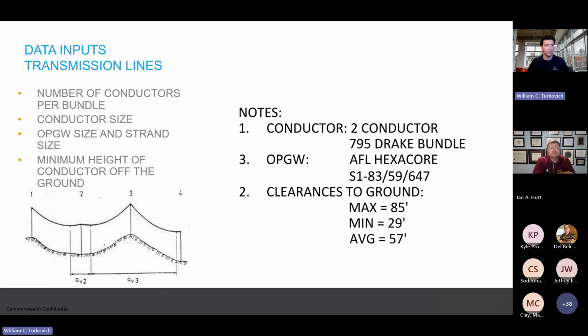The picture on the bottom left shows a transmission line going across bumpy terrain, we'll say. The line sags, and you can see there's a minimum point that's closer or farther from the ground where the lines are. We need to find that point because, as we said, both of these fields are distance driven, meaning the closer they are, the more severe our results will be. You can see we have a max, a min, and an average height for these clearances.